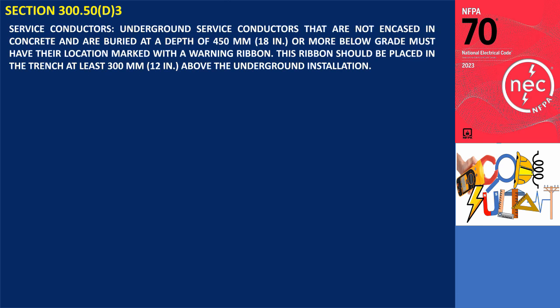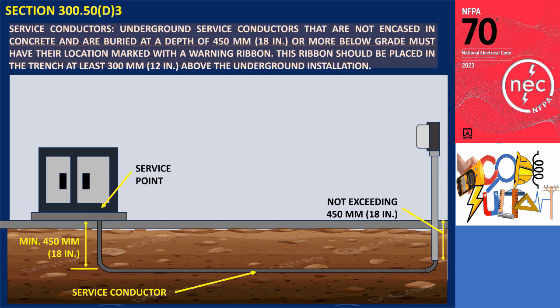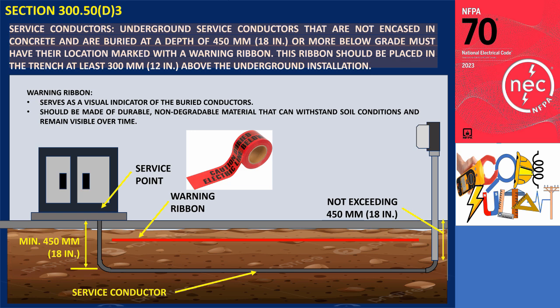Section 300.50(D)3, Service Conductors: underground service conductors that are not encased in concrete and that are buried 450 millimeters (18 inches) or more below grade shall have their location identified by a warning ribbon placed in the trench at least 300 millimeters (12 inches) above the underground installation. This ensures safety and prevents accidental damage during future excavation or construction activities. A warning ribbon serves as a visual indicator of the buried conductors, made of durable, non-degradable material that can withstand soil conditions and remain visible over time, alerting anyone digging in the area to the presence of the buried conductors.